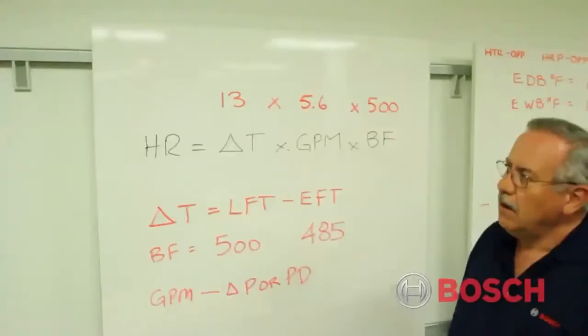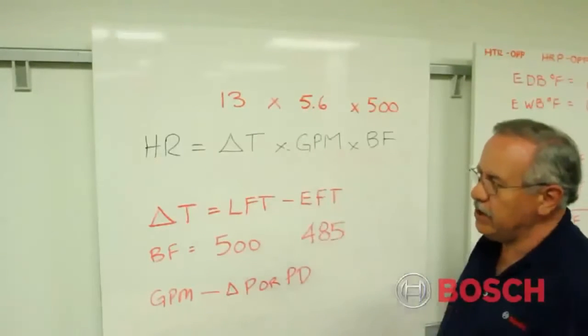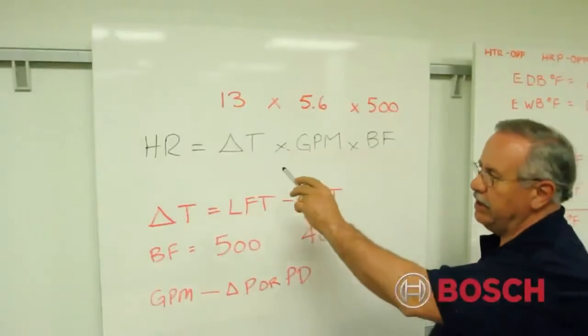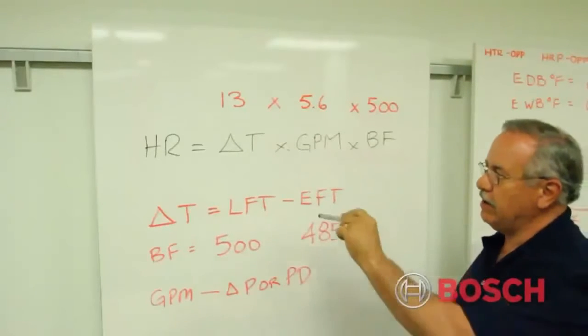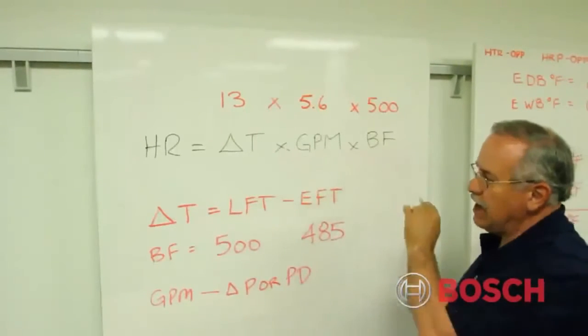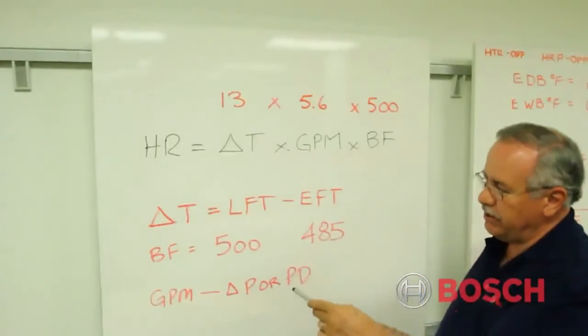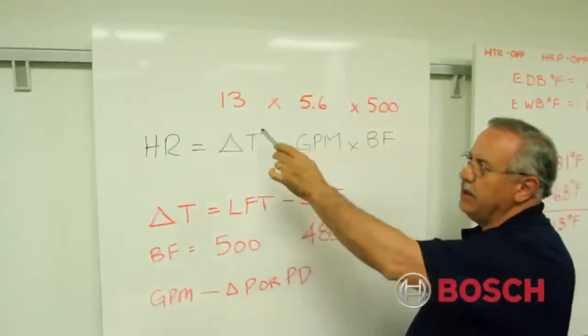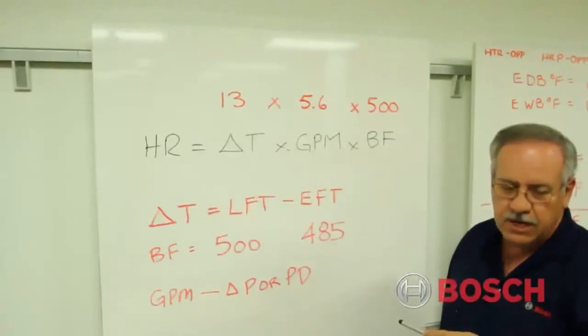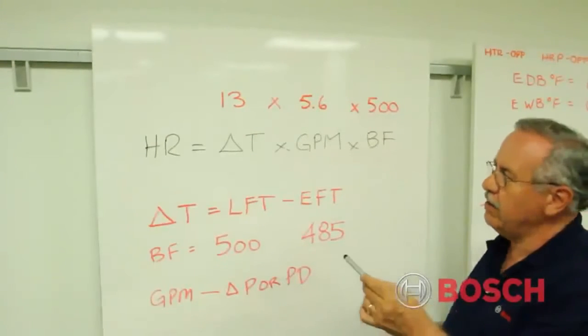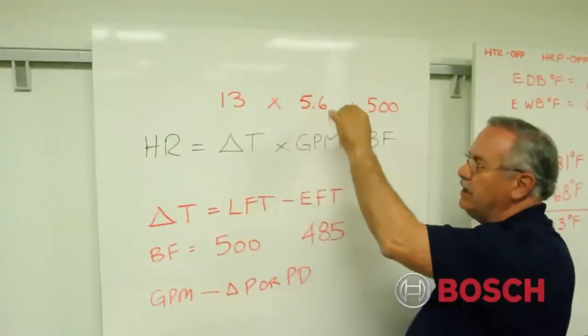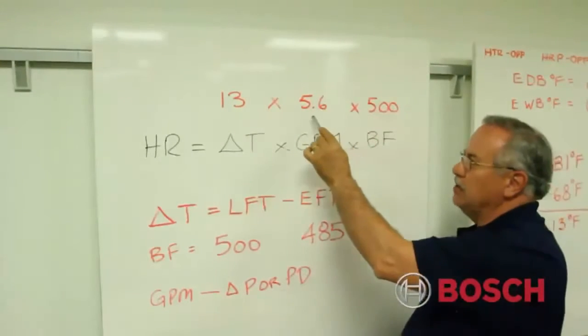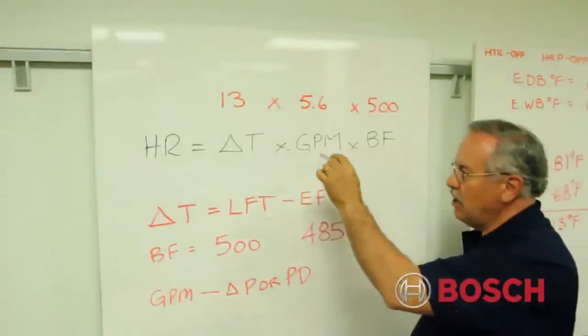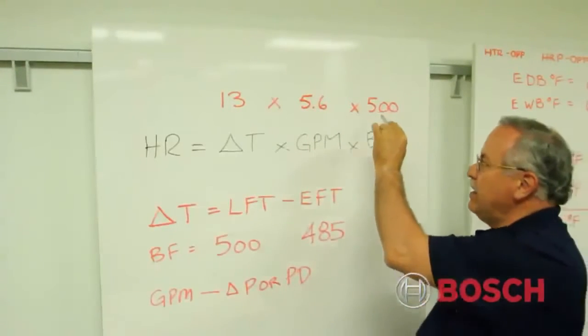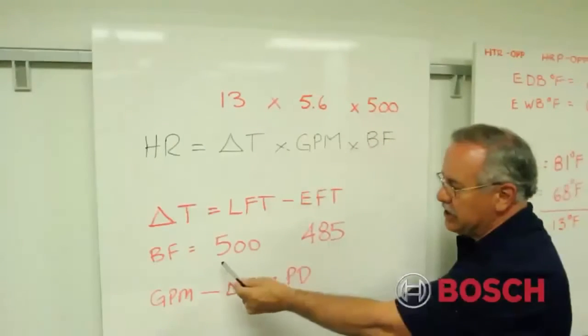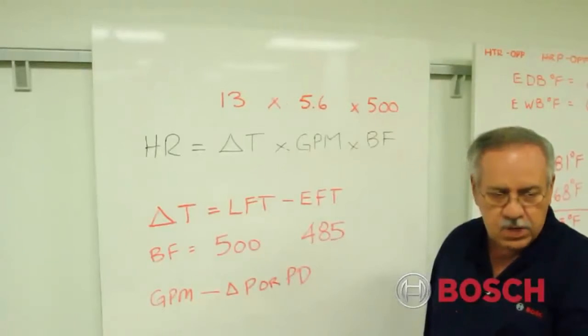pound of pressure drop. Okay, remember earlier we focused on the formula used for calculating heat of rejection in the cooling cycle, and we said that that would be factors of delta T across the heat exchanger times the GPM times the brine factor. Now what we found, what Mark determined from the live equipment, was that he had approximately 13 degrees delta T, or temperature difference from leaving to entering across the heat exchanger, rejecting heat to the earth. We determined from the product literature that 1 psig pressure drop was equivalent to about 5.6 gallons per minute. That's just what we need as one of the factors in our formula. He also substituted for the brine factor 500, which we said earlier was water only, and that's what we were using in this particular case.